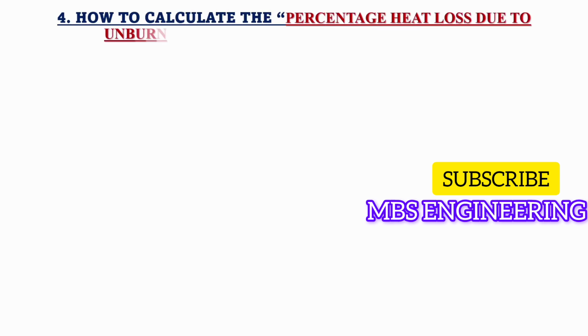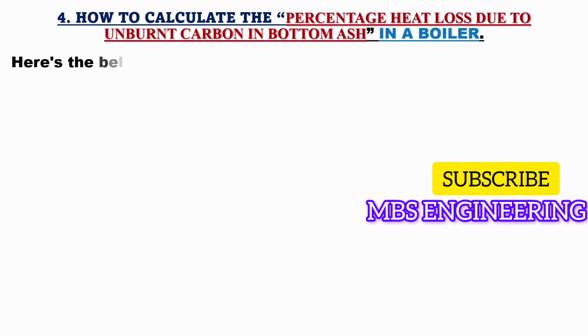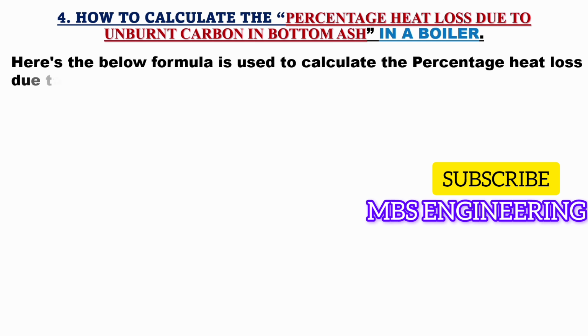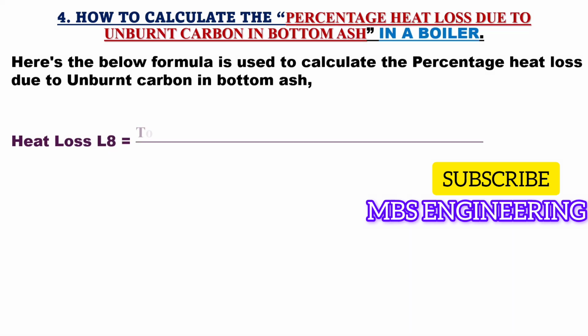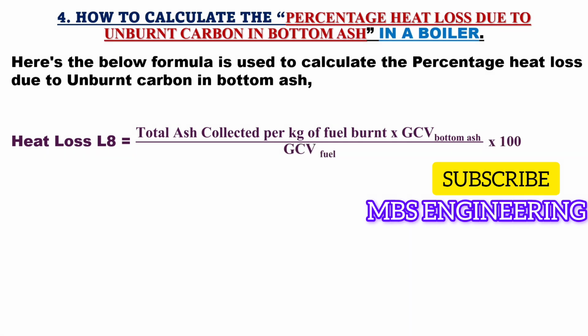Next, we will learn and understand how to calculate the percentage heat loss due to unburnt carbon in bottom ash in a boiler. Here's the formula used to calculate the percentage heat loss due to unburnt carbon in bottom ash in a boiler. Heat loss L8 is equal to total ash collected per kilogram of fuel burnt into GCV of the bottom ash, divided by GCV of the fuel, and then the obtained value is multiplied by 100.